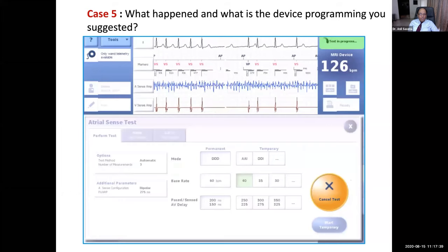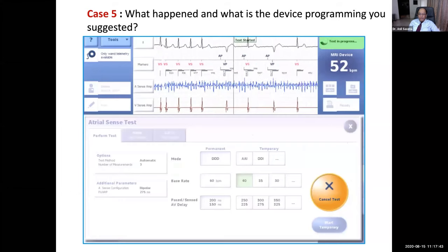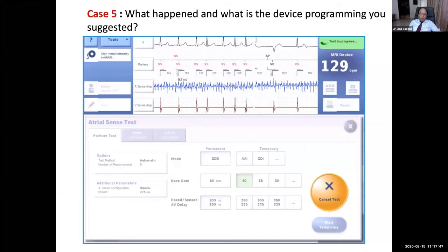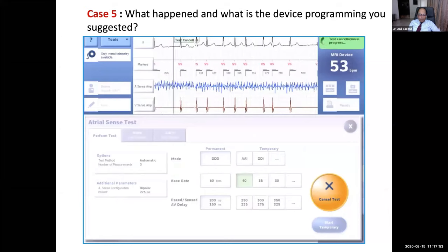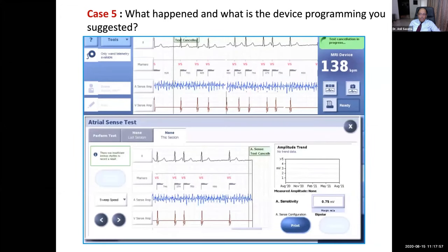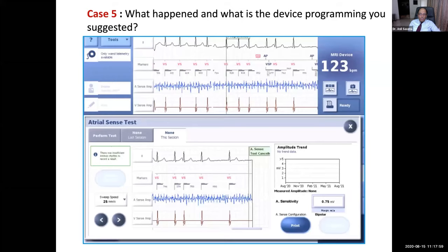The problem is that if you start the atrial sense test in automatic mode, it will start from the currently programmed sensitivity, which was 0.75. So it's not sensing any P wave because the starting sensitivity was too low. We stop the test and start it again.